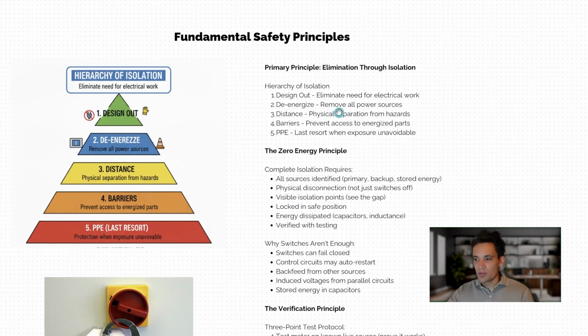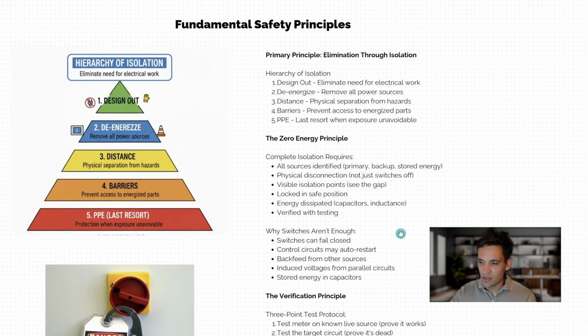Now, while it's all well and good to say de-energize, design out, and avoid working on any live electricity, on complicated projects where there are circuits running everywhere, there is always this challenge of being 100% sure that what you're working on is not live. So this is referred to as the zero energy principle, where all sources, primary, backup, and stored energy are isolated. And this doesn't just apply to electricity, it can apply to mechanical systems as well. If you're working around pumps or generators, you put in place processes so that you can't actually energize the generator when people are working on it.